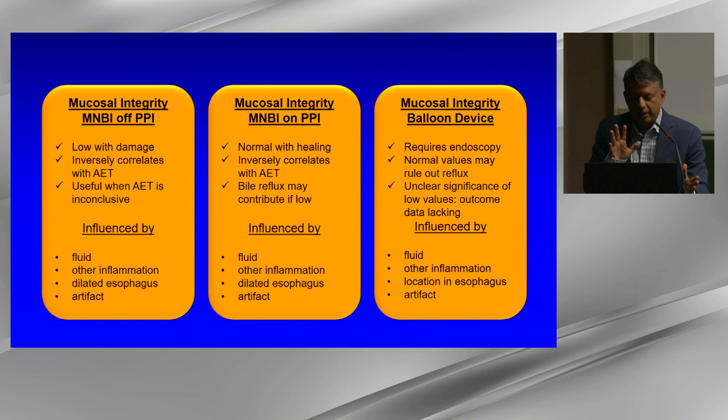The other part about this mucosal integrity balloon device was that it was very clunky. It was very hard, very firm. It has a particular texture that doesn't allow a smooth insertion, and you couldn't lubricate it because that would impact impedance. So there were some inherent issues with this.